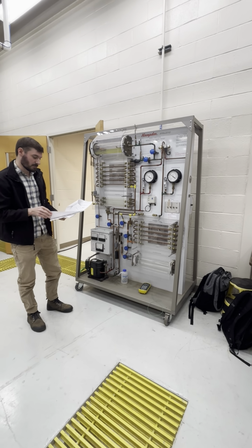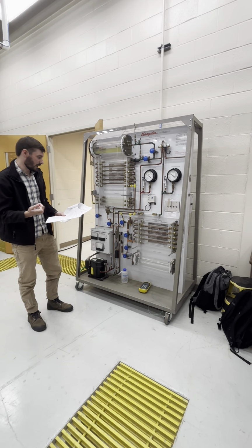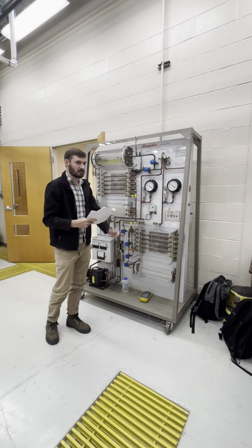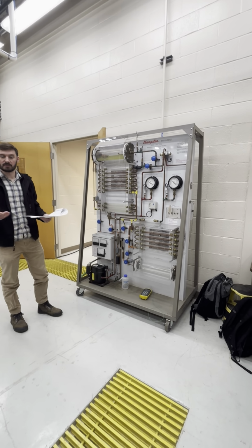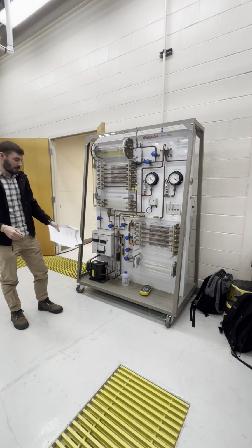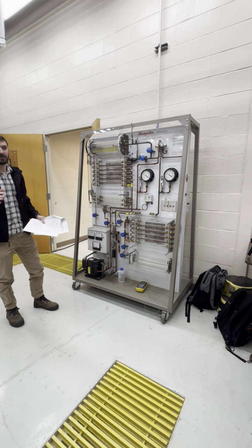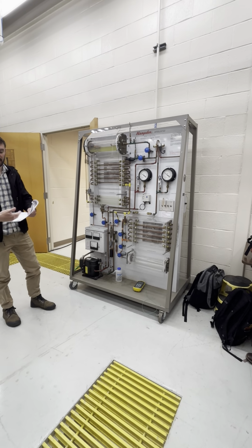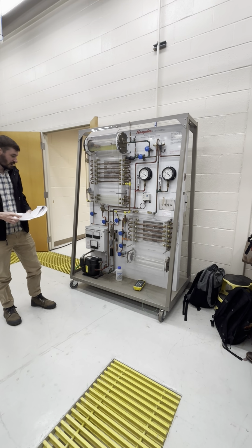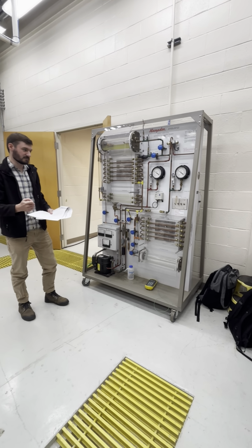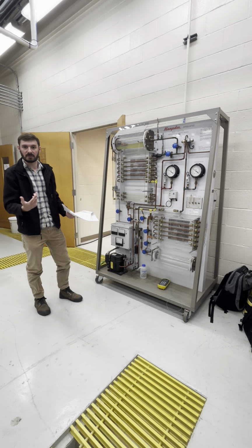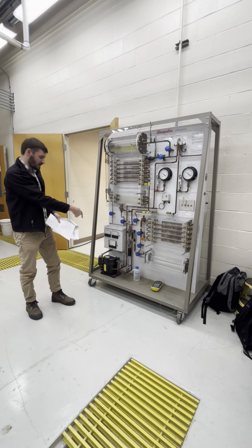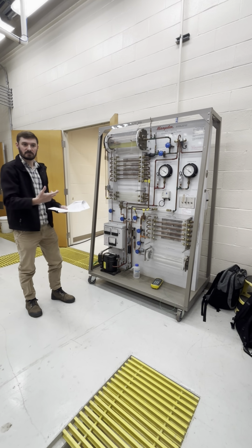You can do something similar, but this is going to be more of a touch sensory thing, where you actually have to touch, let's say, the inlet of the evaporator or the outlet. Is it cool? Is it warm? Is it hot? Be careful with the compressor. That one gets kind of hot, in excess of 100 F, probably 120, something like that. So be careful when you touch that one. Touch it with the back of your hand or something to check it. You'll know if it's too hot to grab because you already have the temperatures. But you basically want to confirm that the temperature is measuring a hot temperature and it feels hot.